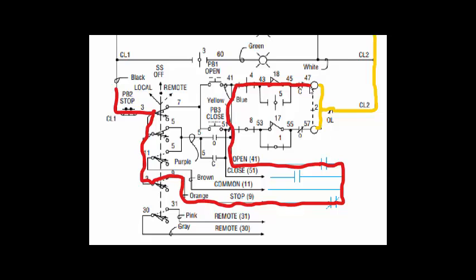is how the open coil for this motor starter is operated remotely. Also what happens is we have a seal-in contact and the way that works remotely is this: when this coil is energized, not only are the three contacts A, B and C phase going to the motor made up, but also this contact here is made up.